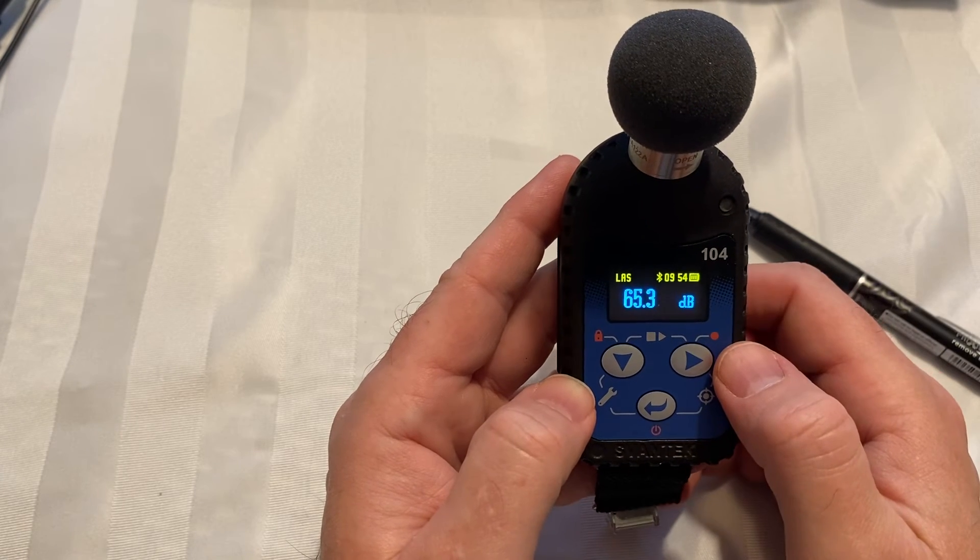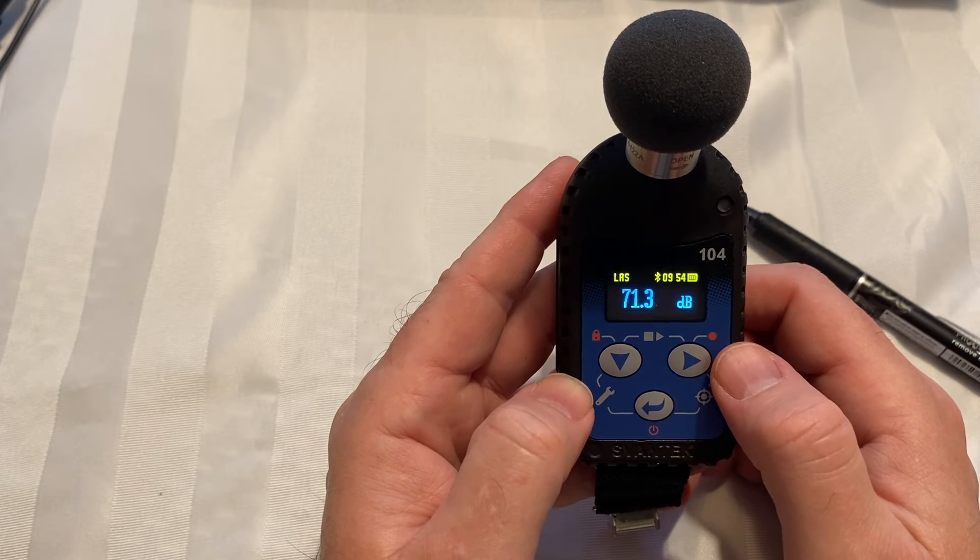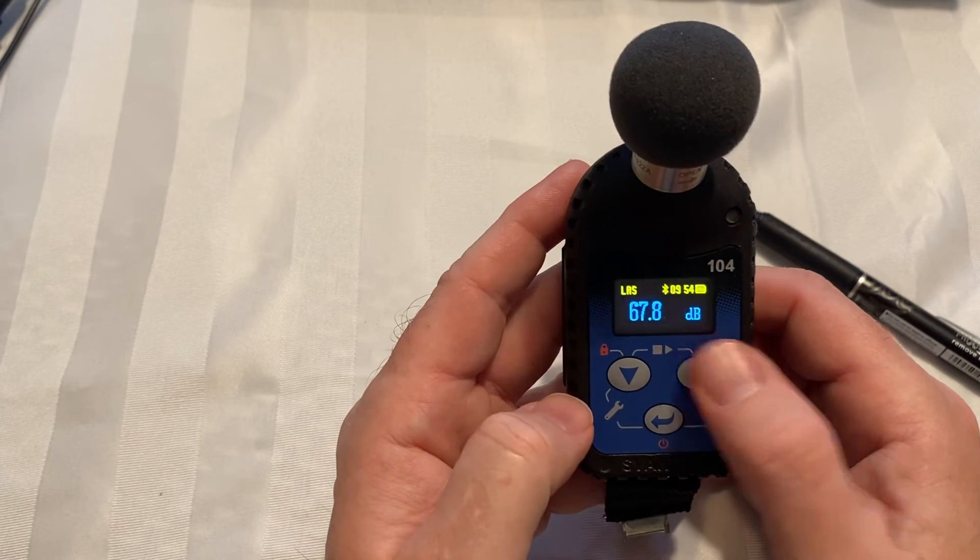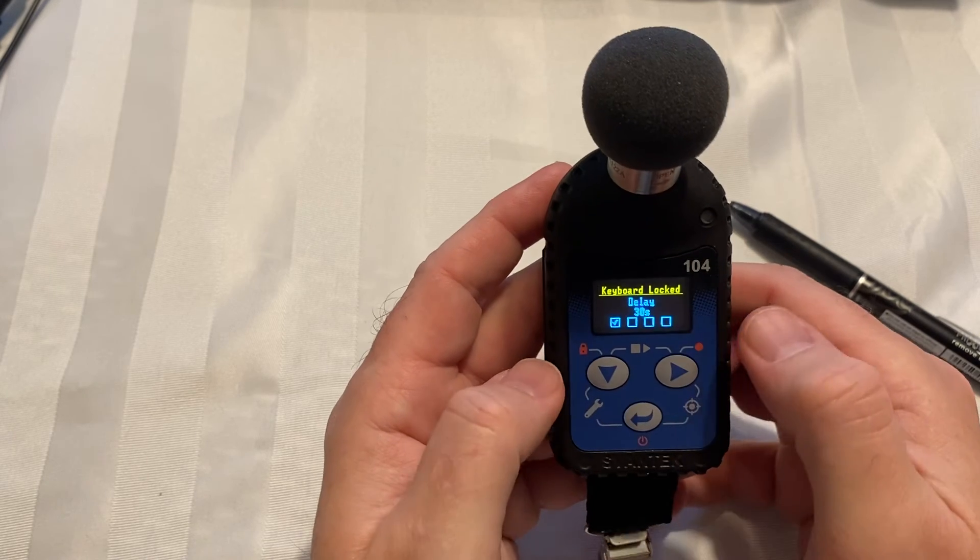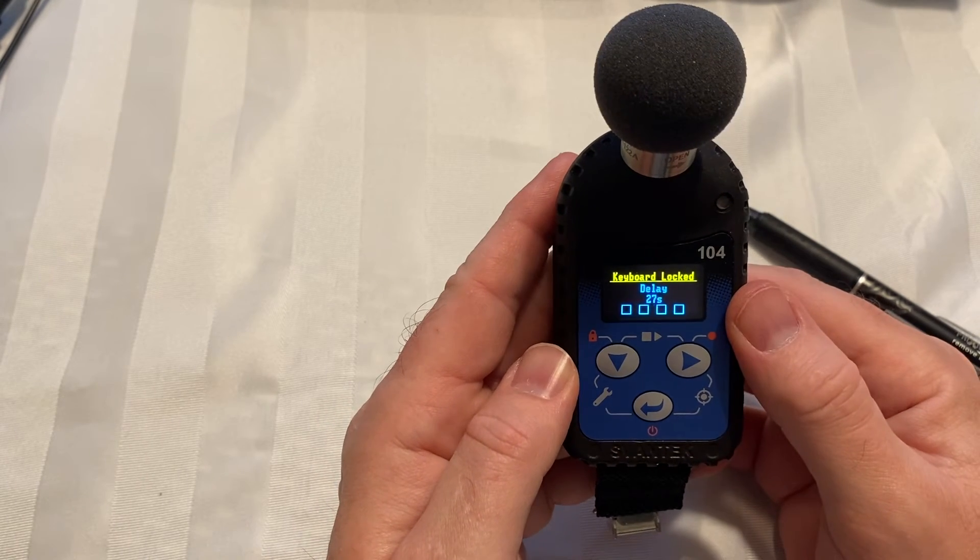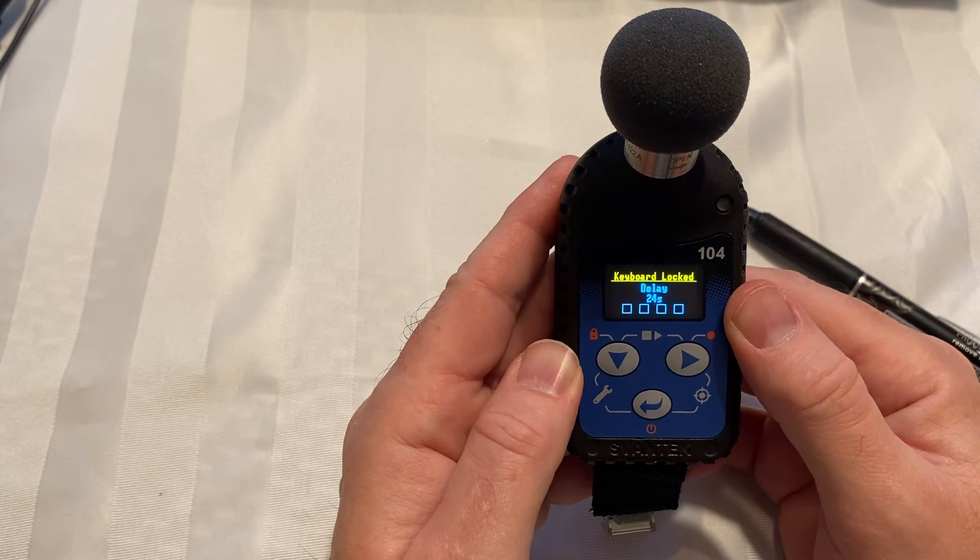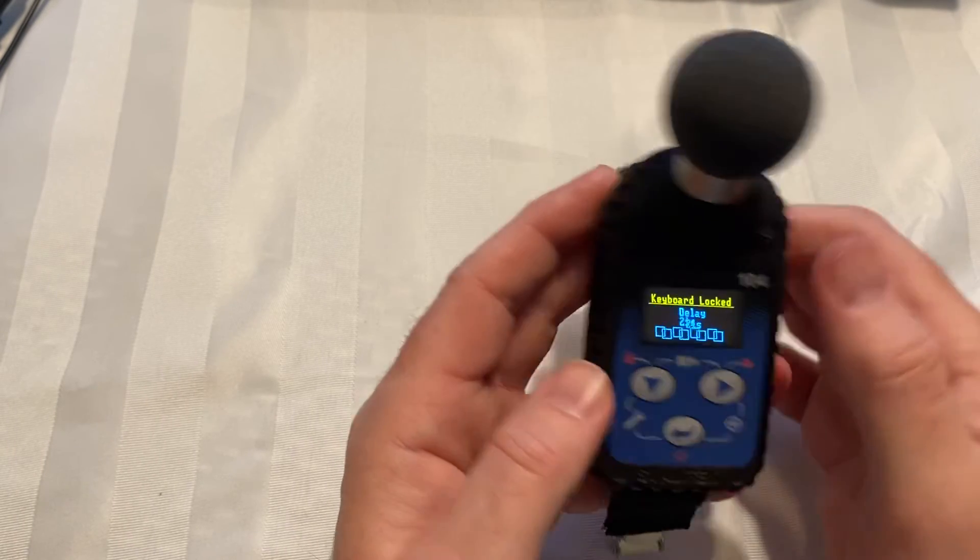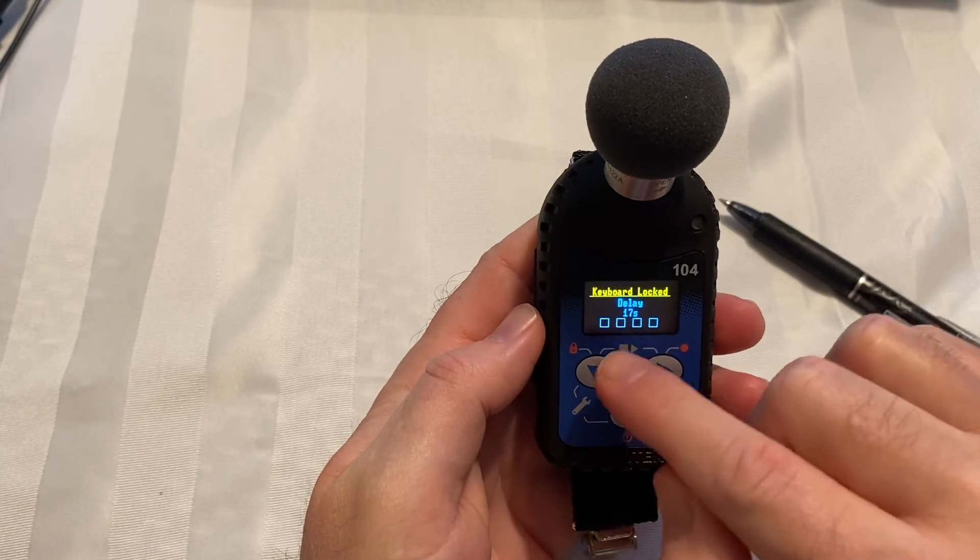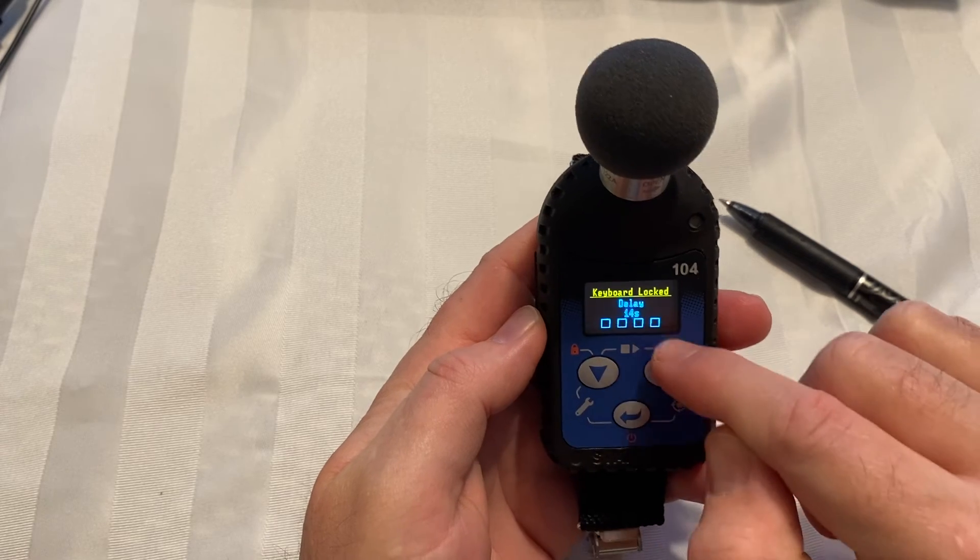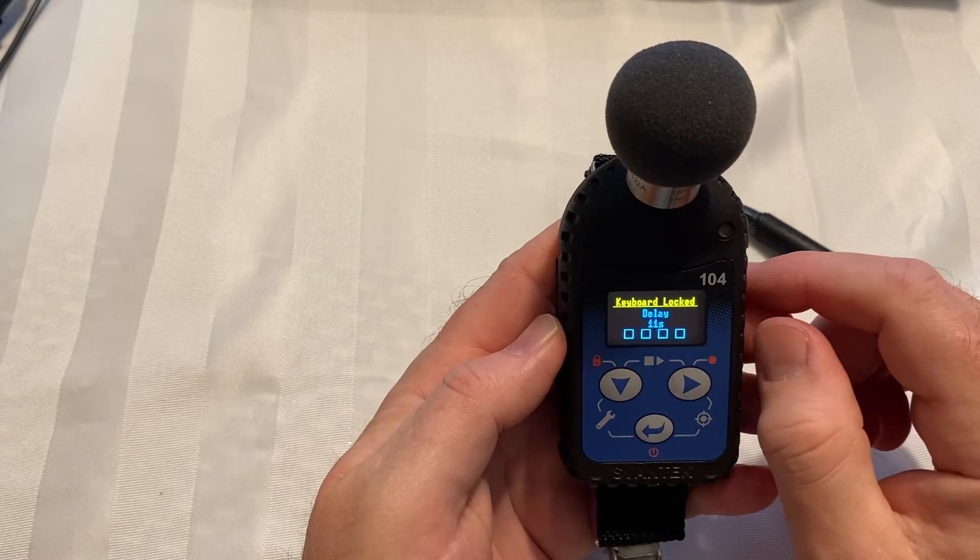Now the last thing I'm going to show you is starting and stopping a run, and that's done with the down and right key at the same time. So when I hit those, I have the software built in with a 30-second delay - you could turn that off or set it shorter. That gives me time to get this clipped on the person. And you'll see now that the keypad is locked as well - it's waiting for the key presses or the code to unlock it.